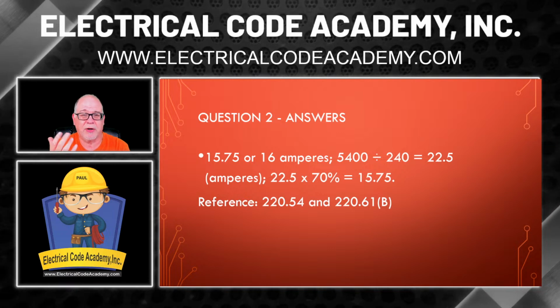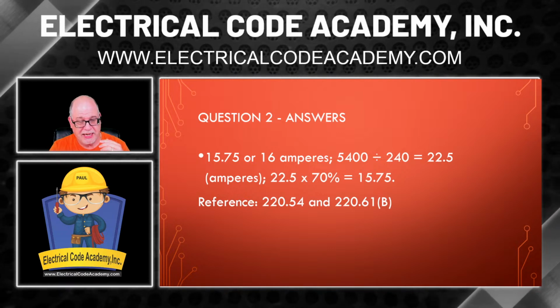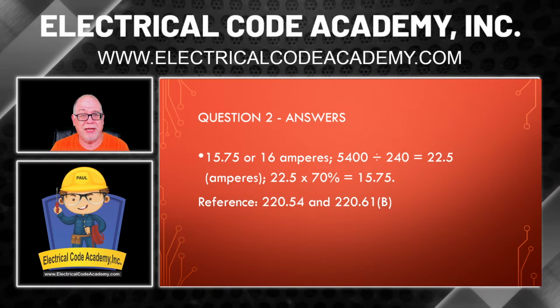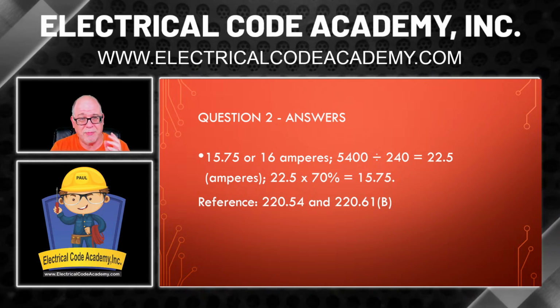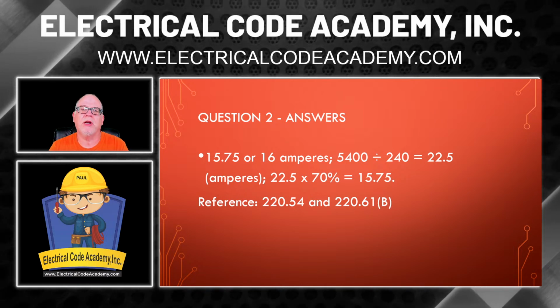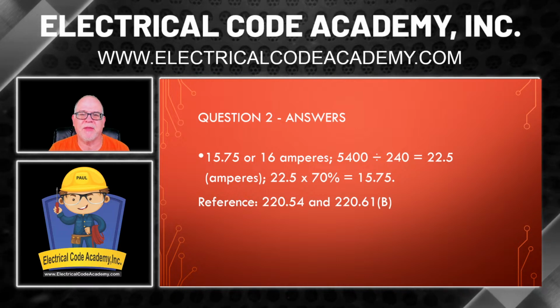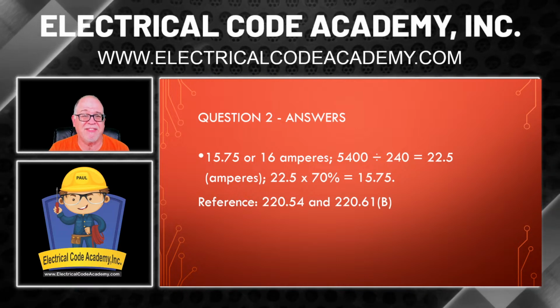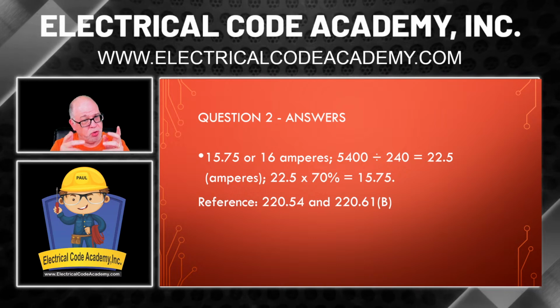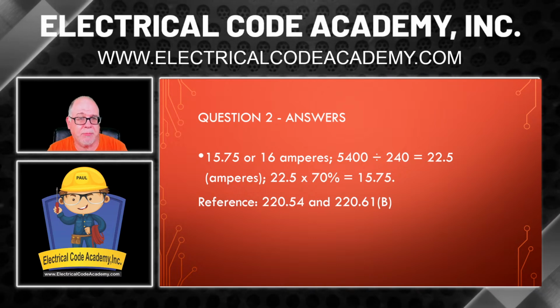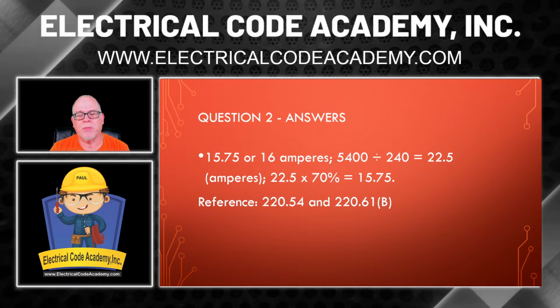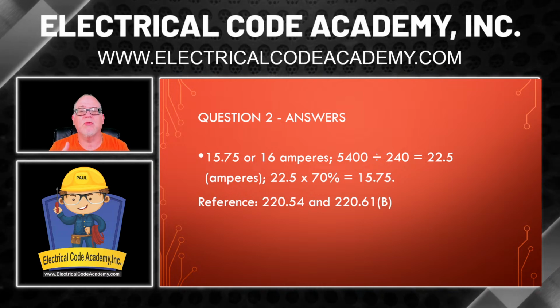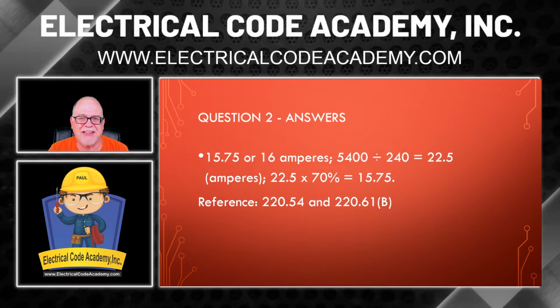Of course, you've got a calculator, probably doesn't matter, but what if that calculator went dead? So much easier to work decimals with decimals, right? Anyway, so 22.5 times 70% is 15.75, and that is the actual contribution. Now, since we're dealing with amps, the code does allow you, if it's 0.5 or greater in amps, to round it up to the next available size and use that.